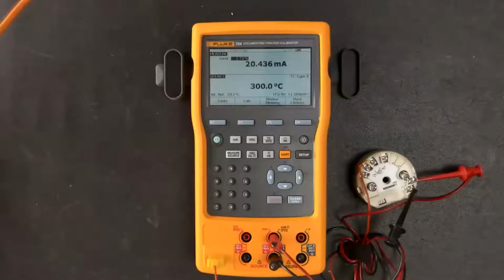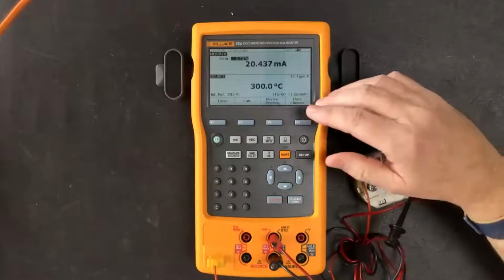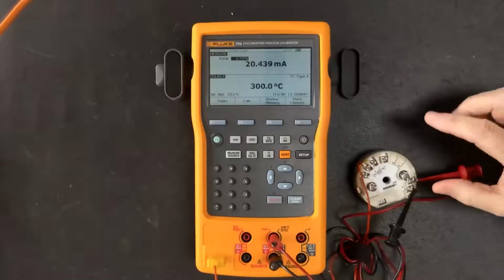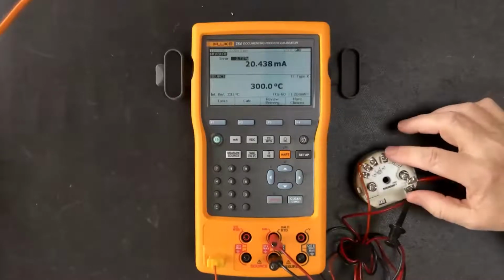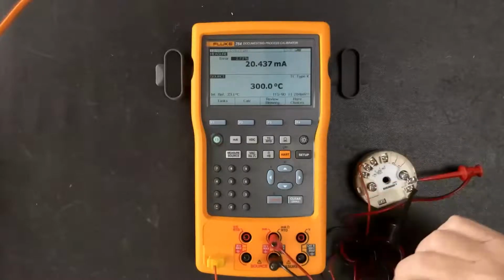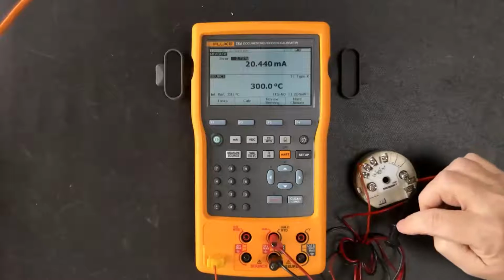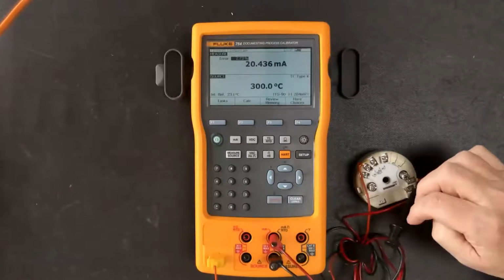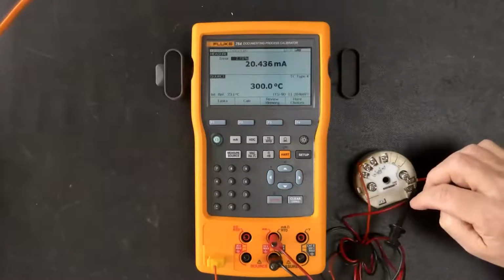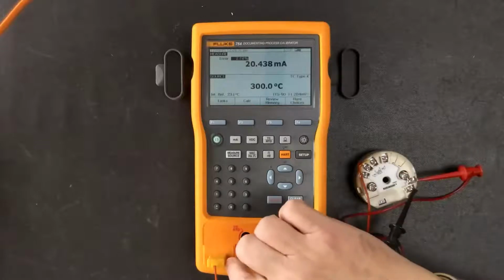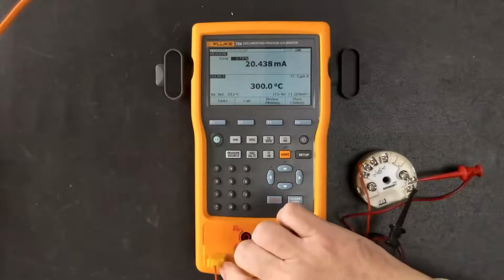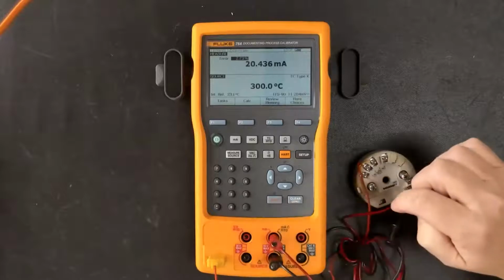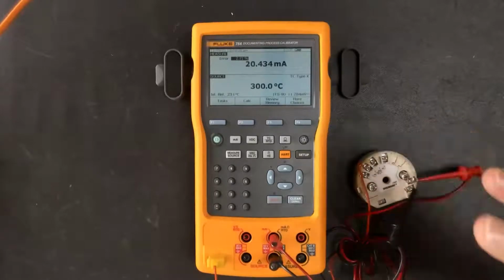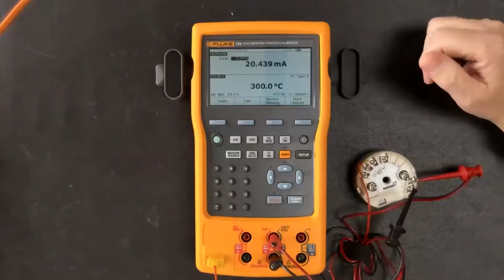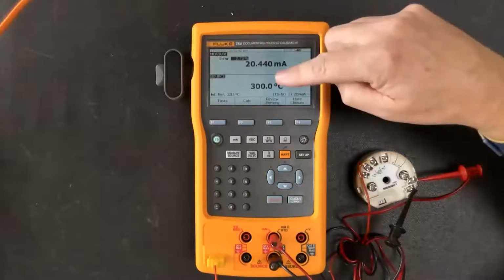What we've got over here is a Fluke 754, and we are connecting to a Rosemount 644 transmitter. We're providing loop power through the 4-20 milliamp jacks, and we can also talk HART through this milliamp loop here. And then we're also sourcing or simulating a thermocouple signal to the transmitter, so we can do a full calibration with this setup here. So if you notice, we've got our source and measure set up.